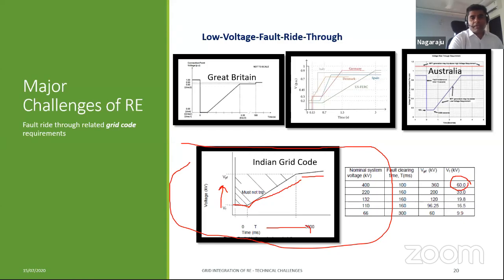So the entire region must not trip. You can see here, must not trip. And below this solid line, it can trip. Similar philosophy applies across other countries, Great Britain, Australia, and the middle picture shows it for some other countries. So that is the fault ride through requirement by the grids.